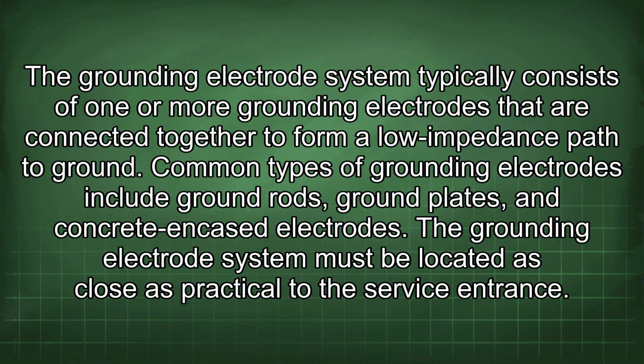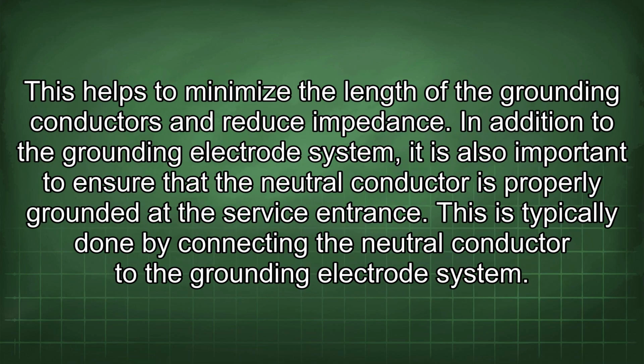The grounding electrode system typically consists of one or more grounding electrodes that are connected together to form a low impedance path to ground. Common types of grounding electrodes include ground rods, ground plates, and concrete encased electrodes. The grounding electrode system must be located as close as practical to the service entrance. This helps to minimize the length of the grounding conductors and reduce impedance.